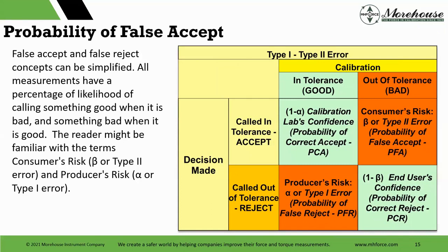People might have heard of type 1 and type 2 error. You might have heard of consumer and producer's risk, but false accept and false reject concepts can be simplified. All measurements have a likelihood of calling something good when it is bad and something bad when it is good. The reader might be familiar with the terms consumer and producer, type beta, type 2, or alpha, type 1 error. And what's important is we can never know. If you watch the other webinars, we can never know the actual value of what we're measuring.